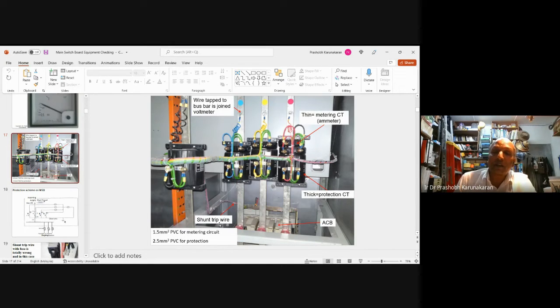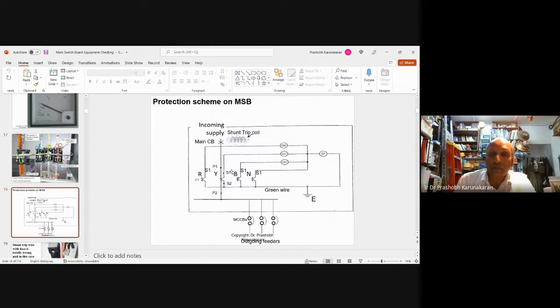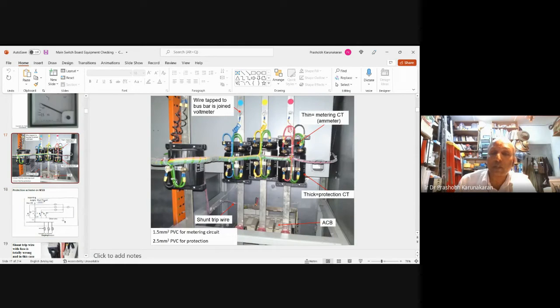So that's how this circuit works. The red, yellow, blue will go to the OC. OC comes out, joins together to the S1 of the neutral CT, all go to the earth fault relay. This is the OC relay and earth fault relay. The other side of the earth fault relay, all green wire, going to the other side of all the coils, all the CTs have green wire, the earthing wire.